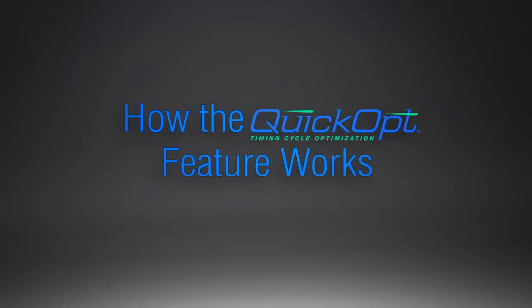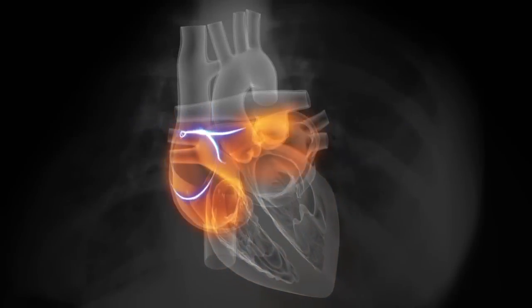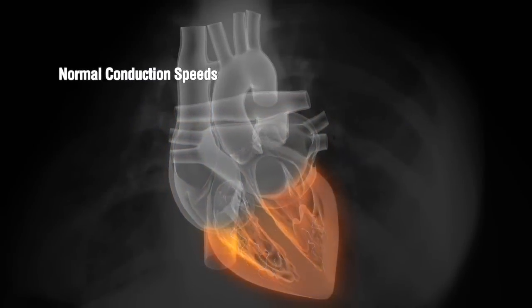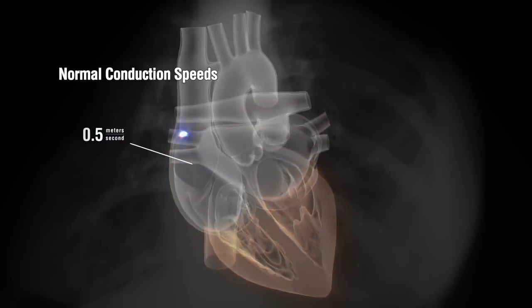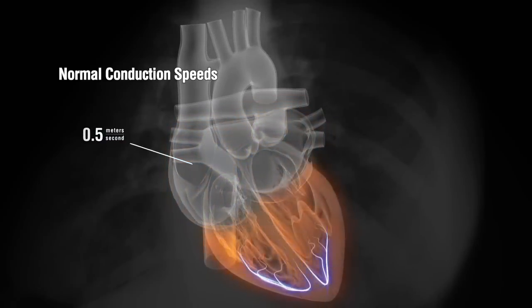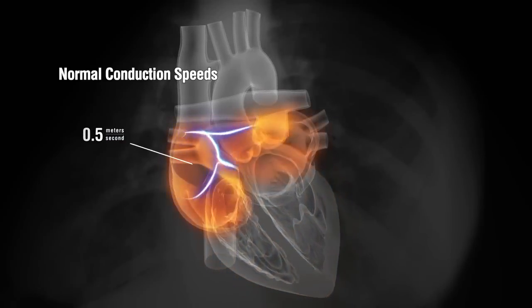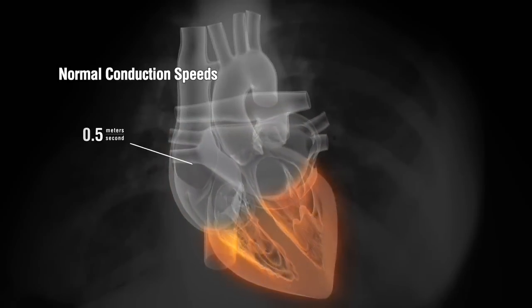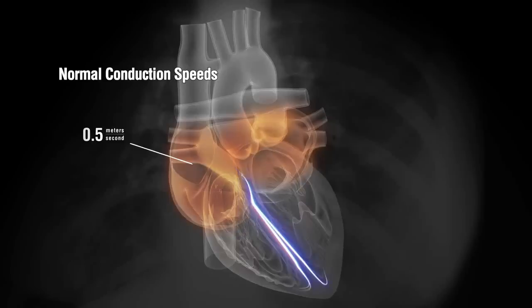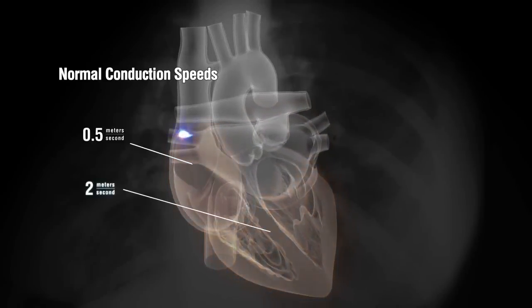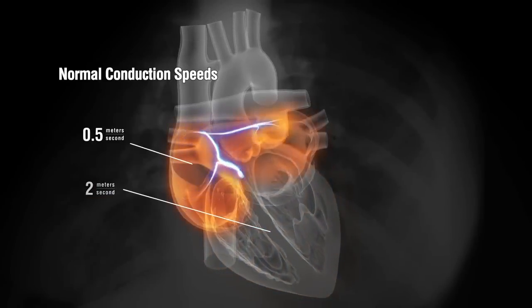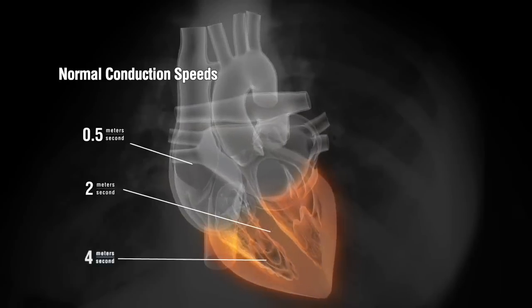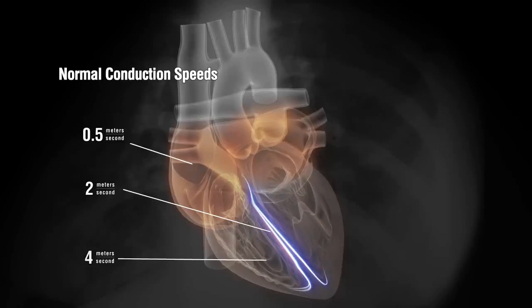How the QuickOpt feature works: QuickOpt optimization measurements are based upon the heart's conduction properties. It is well known that the atria and ventricles conduct at a speed of approximately one-half meter per second on average. While the impulse slows down through the AV node, it accelerates to a speed of approximately two meters per second through the bundle branches and rapidly accelerates again to approximately four meters per second in the Purkinje network.